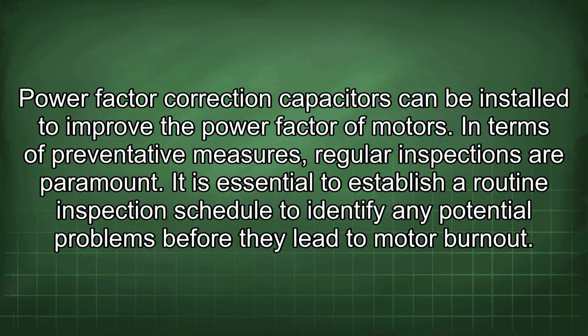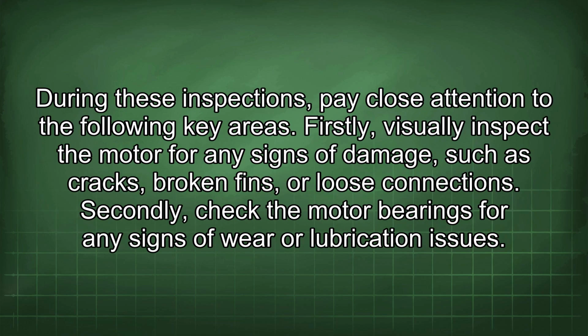In terms of preventative measures, regular inspections are paramount. It is essential to establish a routine inspection schedule to identify any potential problems before they lead to motor burnout. During these inspections, pay close attention to the following key areas. Firstly, visually inspect the motor for any signs of damage, such as cracks, broken fins, or loose connections.